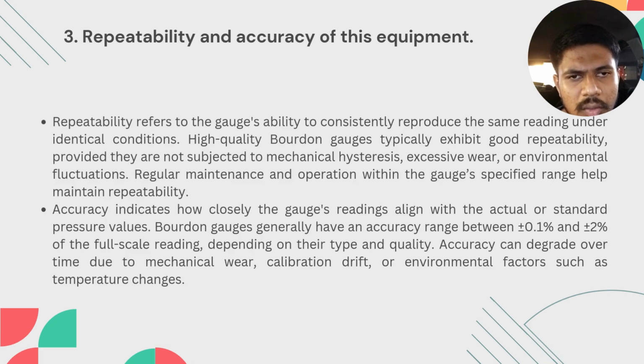Accuracy indicates how close the gauge reading aligns with the actual or standard pressure value. Bourdon gauges generally have an accuracy range between plus minus 0.1% and plus minus 2% of the full scale reading, depending on their type and quality. Accuracy can degrade over time due to mechanical wear, calibration drift, or environmental factors such as temperature change.